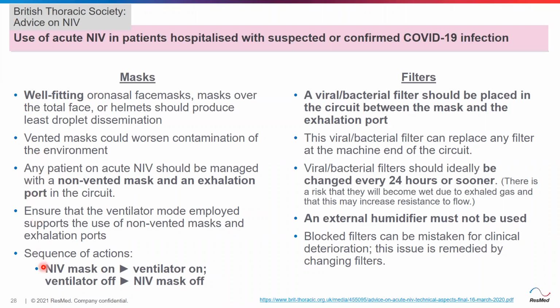The sequence of action should be: first put the mask on the patient, then switch on the ventilator. While stopping the therapy, first switch off the ventilator, then remove the mask. So mask on, then switch on the ventilator; switch off the ventilator, and then remove the mask. This ensures the least probability of dispersion or aerosolization, and would save the healthcare professional or the caregiver.